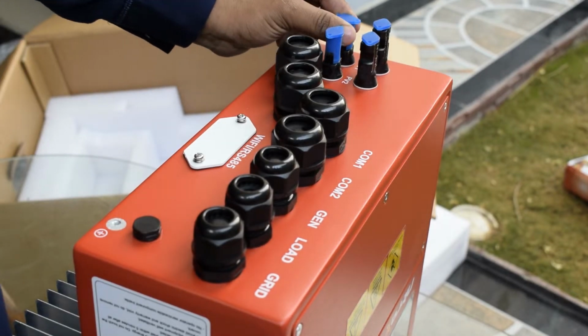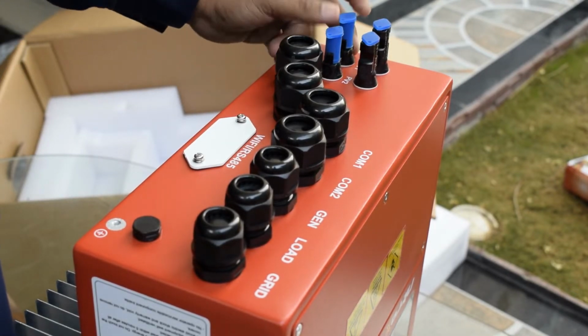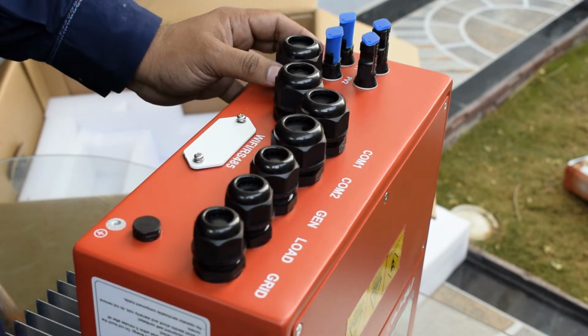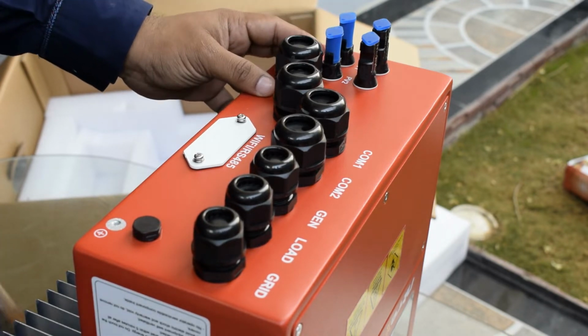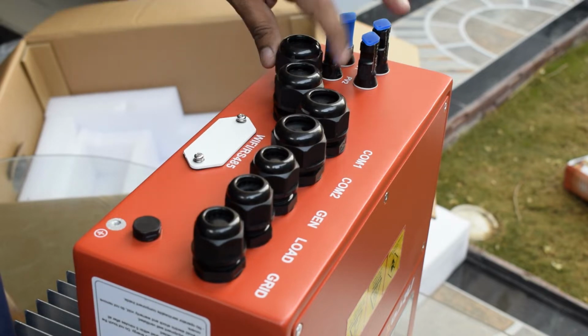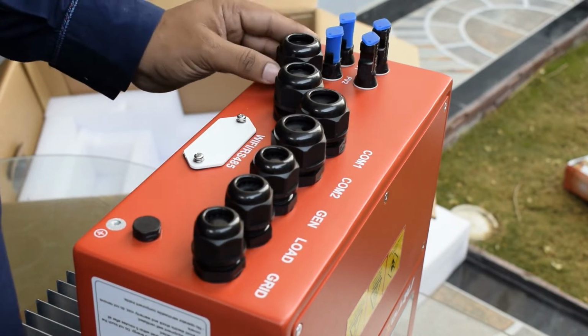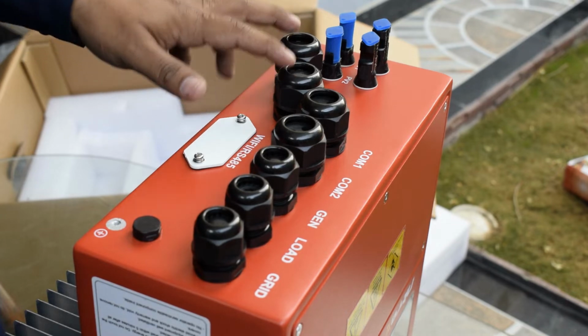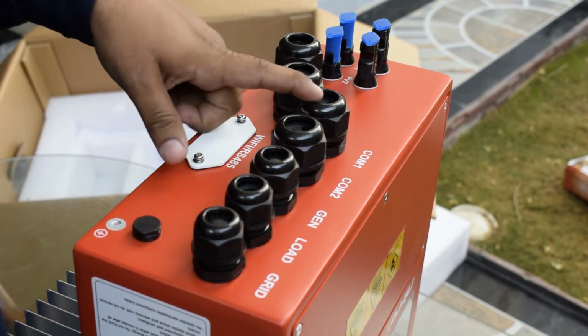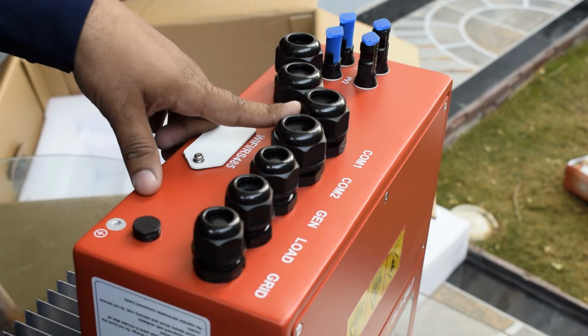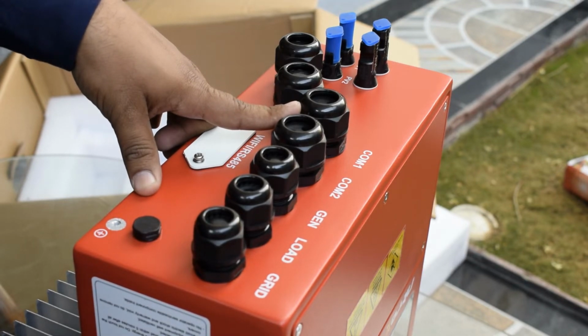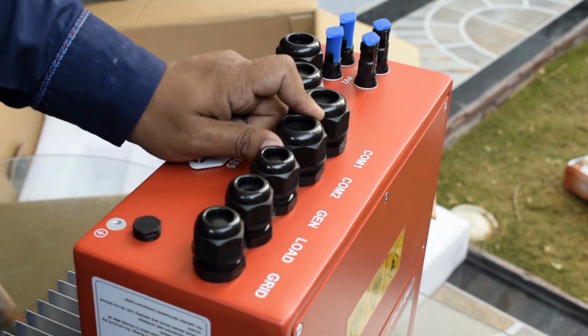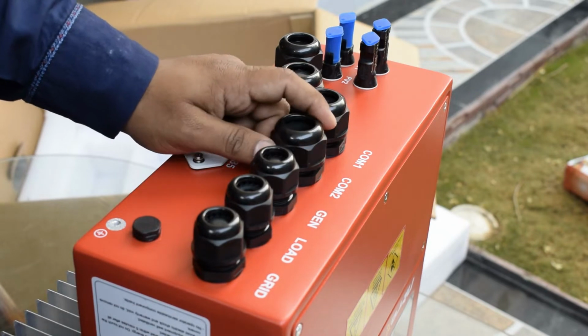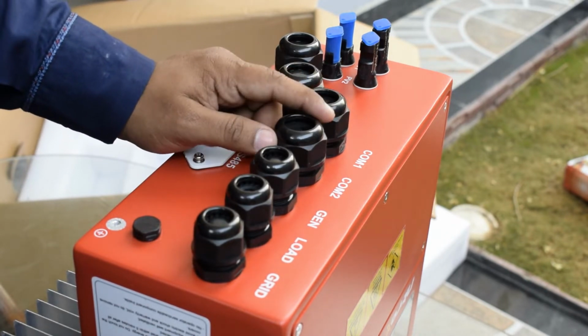These are the solar PV ports. We can make 2 strings of 5 panels or 4 panels, depending upon the configuration. This socket is for the battery minus and plus. This socket is for the communication cable for the zero export device, for calculating the home load and solar production. And this communication port is to connect parallel inverters or to connect with the computer.